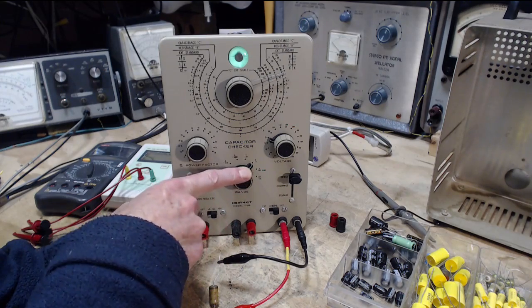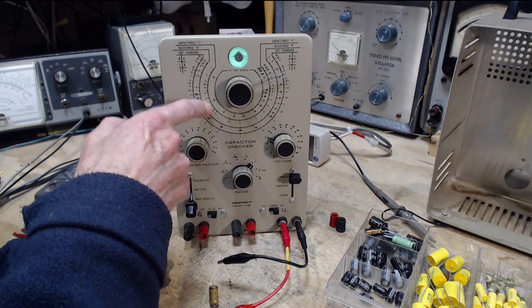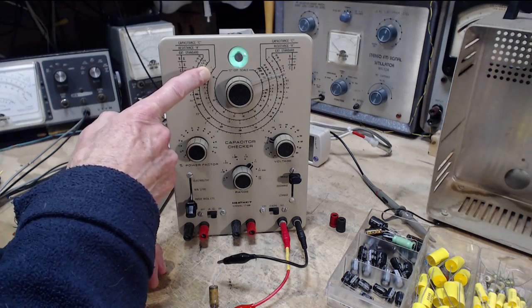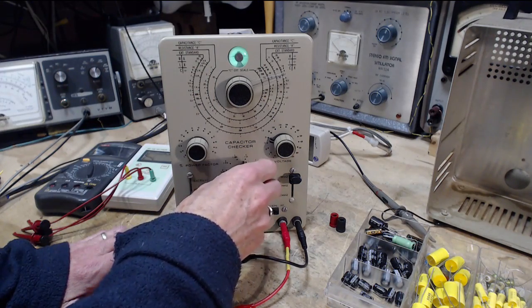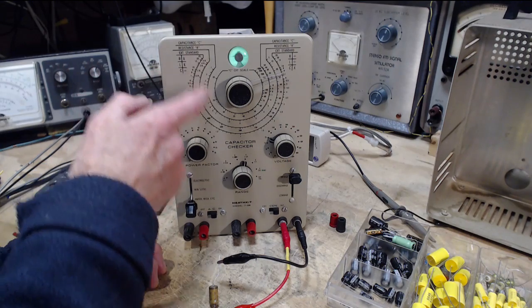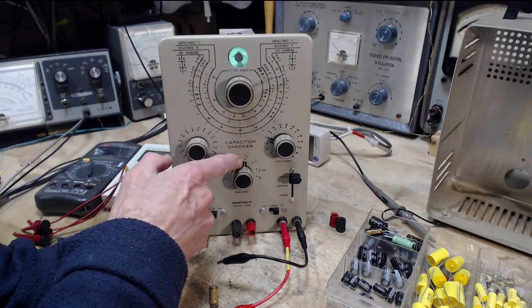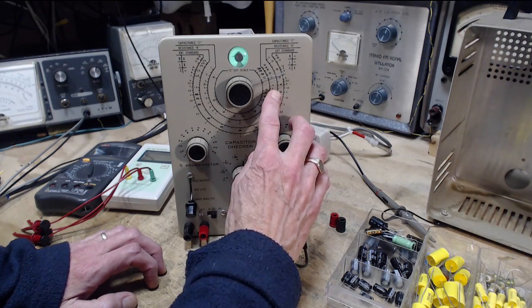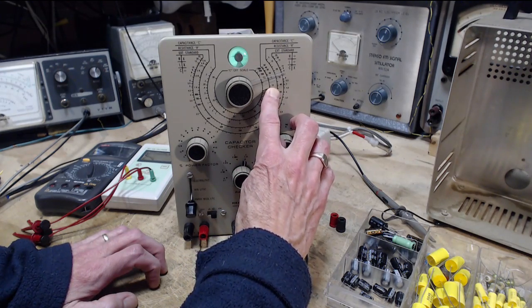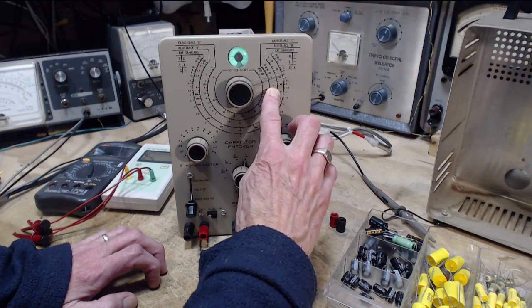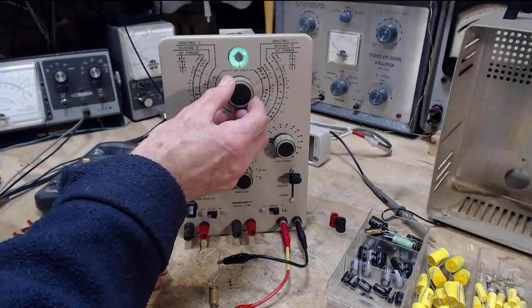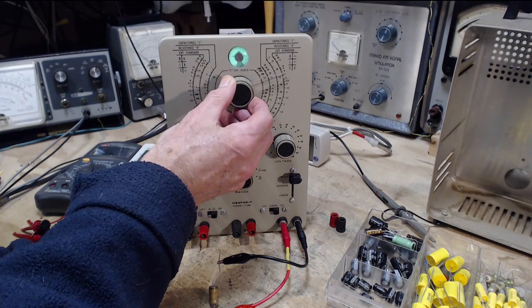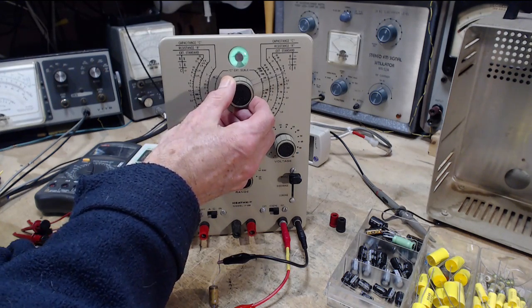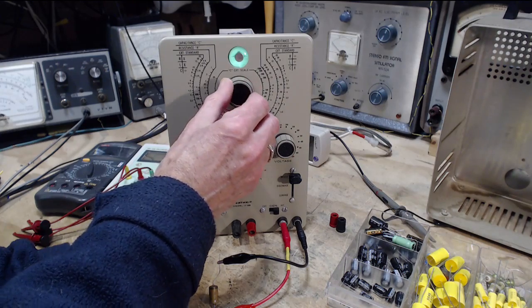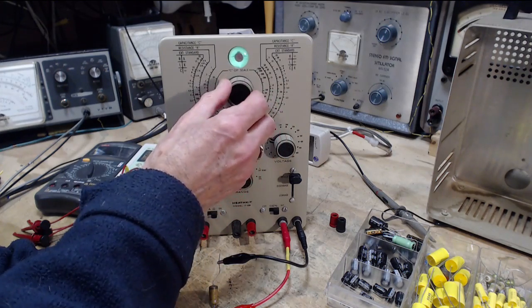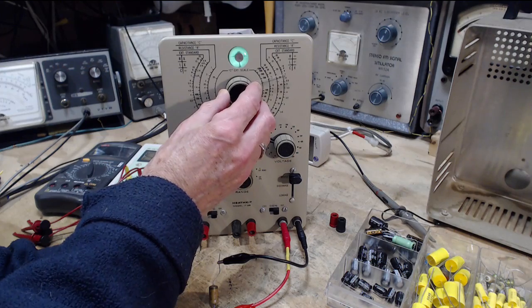So on the times one scale, 0.1 is sitting way up here. 0.01, that's a change of 100. So I'd say 0.01 times 10 gives you 0.1, so this is the spot. So this should be open. It is open, again it's a little high. There's some calibration in here, maybe that's the thing to do, go through the calibration procedures.